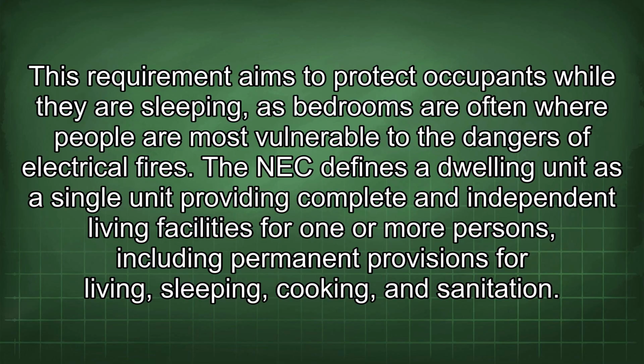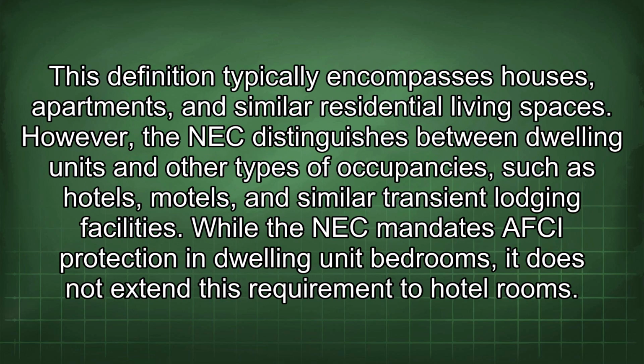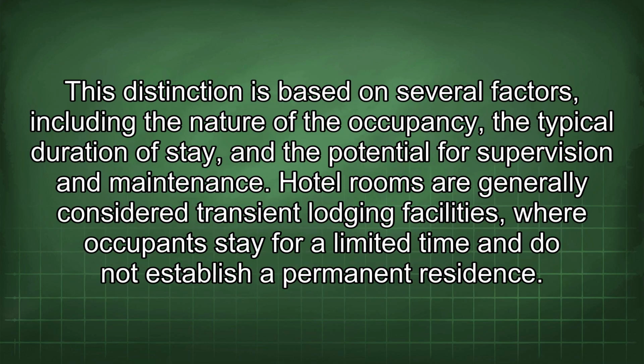The NEC defines a dwelling unit as a single unit providing complete and independent living facilities for one or more persons, including permanent provisions for living, sleeping, cooking, and sanitation. This definition typically encompasses houses, apartments, and similar residential living spaces. However, the NEC distinguishes between dwelling units and other types of occupancies, such as hotels, motels, and similar transient lodging facilities. While the NEC mandates AFCI protection in dwelling unit bedrooms, it does not extend this requirement to hotel rooms. This distinction is based on several factors, including the nature of the occupancy, the typical duration of stay, and the potential for supervision and maintenance.